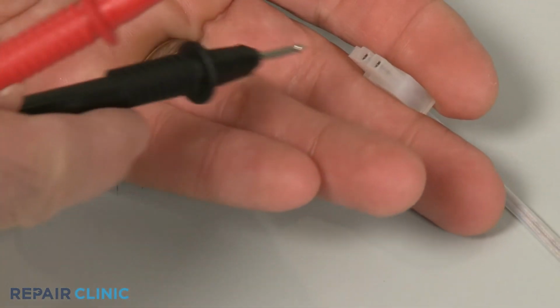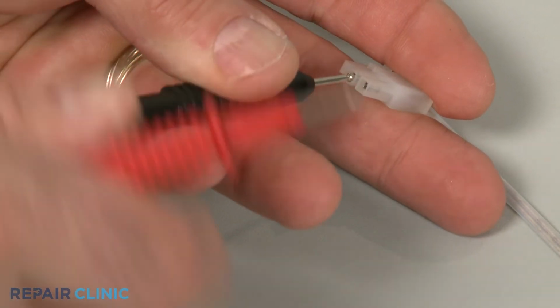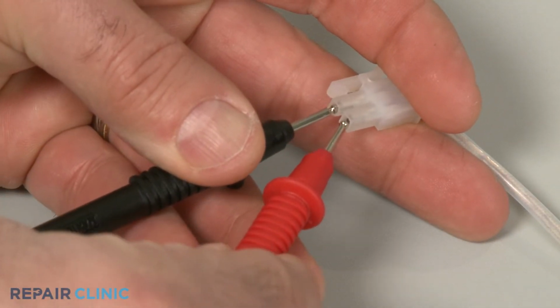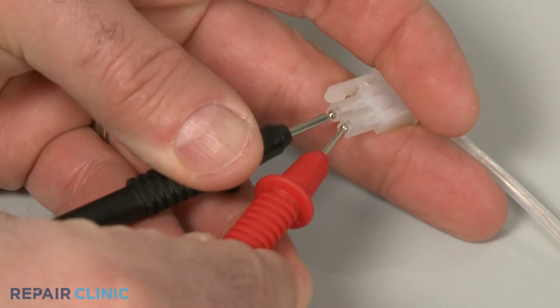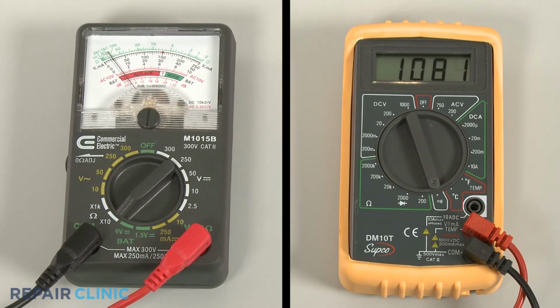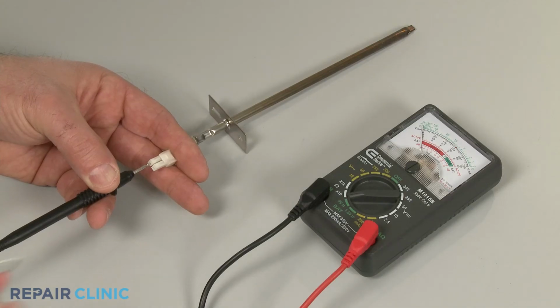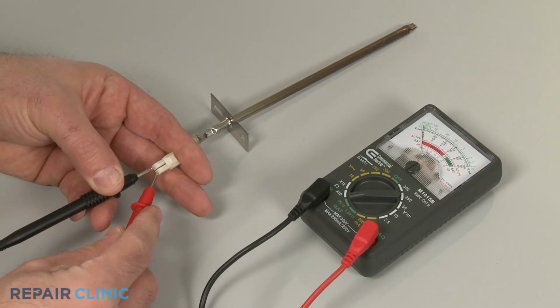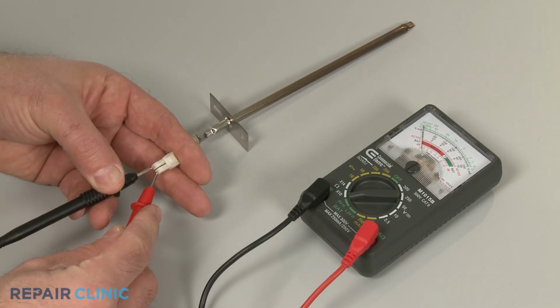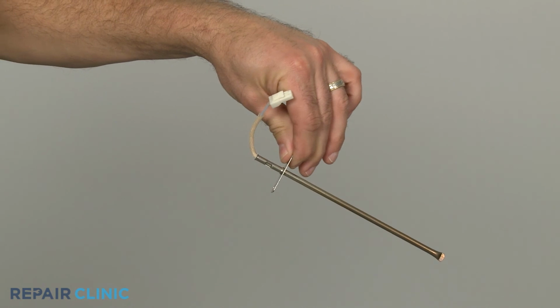Now use a probe to touch one of the sensor's terminals, and the second probe to touch the other terminal. If the sensor is functioning properly, the meter should read between 1,000 and 1,100 ohms of resistance at room temperature. Be aware that the high resistance of the sensor will probably prevent a meter tone. A significantly different reading strongly suggests that the sensor is malfunctioning and will need to be replaced.